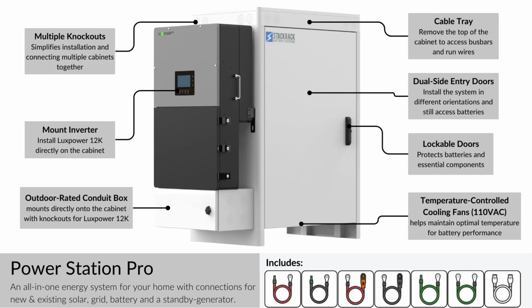So now talking about some of the features that make Power Station Pro really special. Multiple knockouts along the top conduit box for lots of flexibility for installation and connections. The ability to mount the Luxpower inverter directly on the side of the cabinet. The ability to put the outdoor rated conduit box on the side of the cabinet and have a connection from the inverter using bushings that are provided into the cabinet, so battery cables and wires can travel within the inverter into the cabinet without any additional conduit. On the top of the cabinet, the roof can be removed, and that gives you access to the bus bars. And for paralleling different cabinets together, you have dual side entry doors, which allows you to orient the cabinet either way based on what's best for the inverter and the setup.